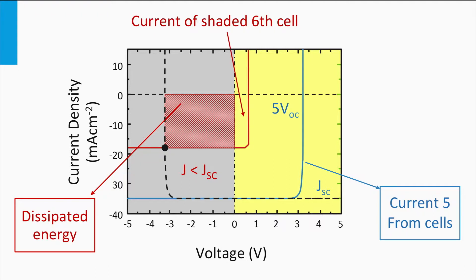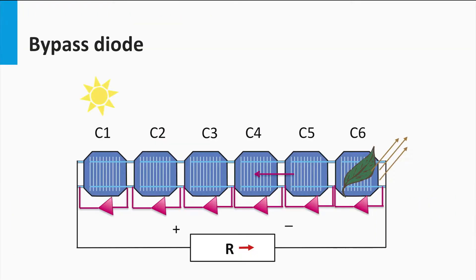The temperature can increase to such a critical level that the encapsulation material cracks or other materials wear out. High temperature conditions also lead to a decrease of PV output. This can be prevented by including bypass diodes in the module. A diode blocks current in one direction when under negative voltage but conducts current when under positive voltage. If no cell is shaded, no current flows through the bypass diodes. When one cell is shaded, the bypass diode starts to pass current, allowing the current to go around the shaded cell so the module can still produce the current equal to that of a non-shaded single solar cell.